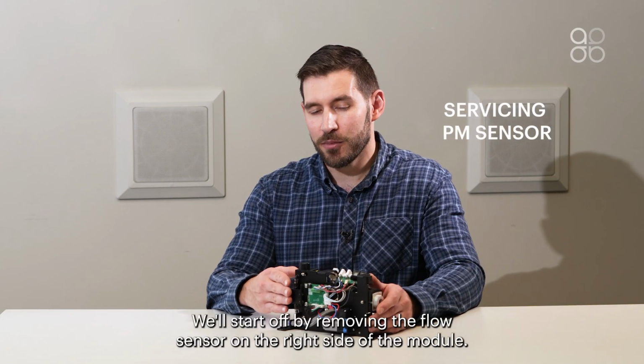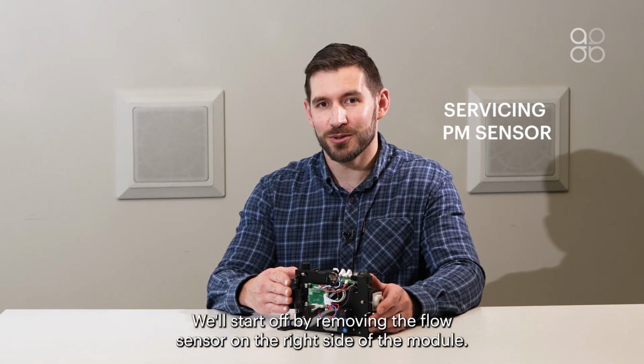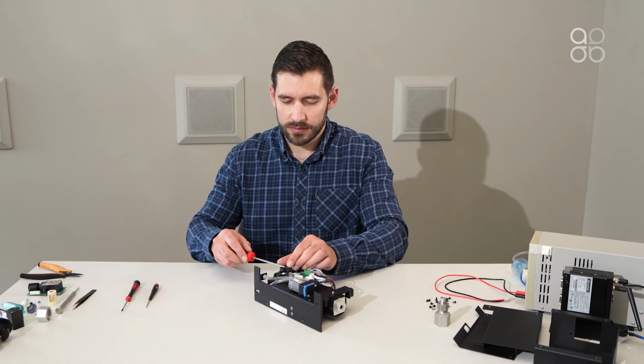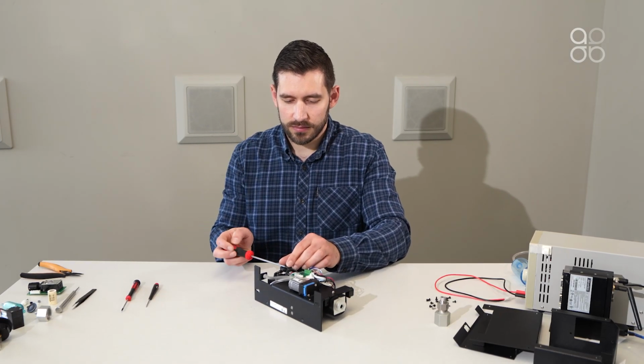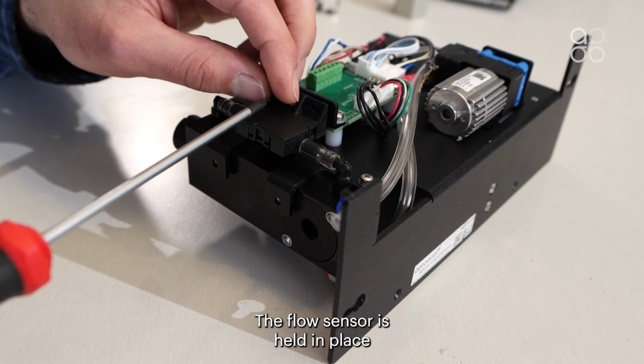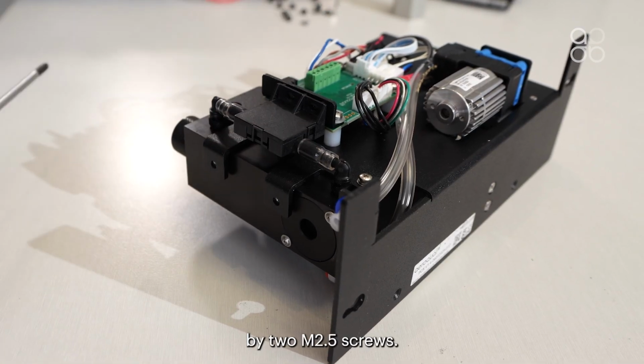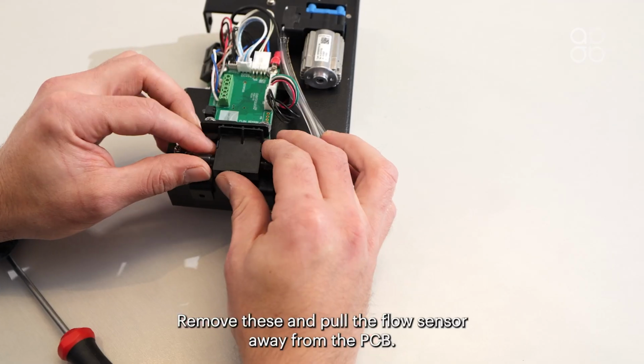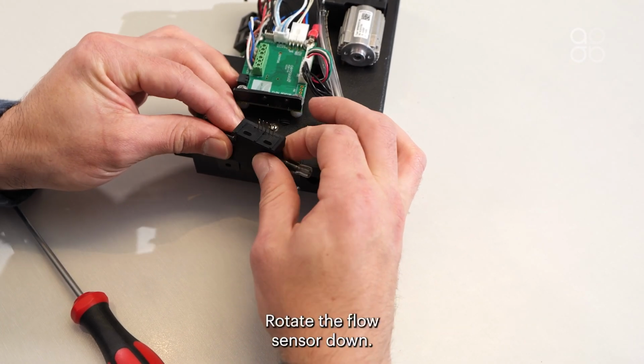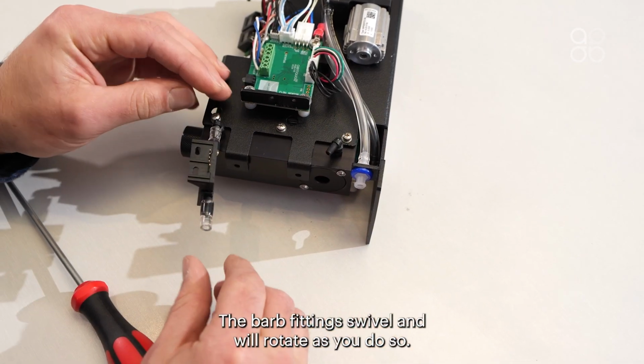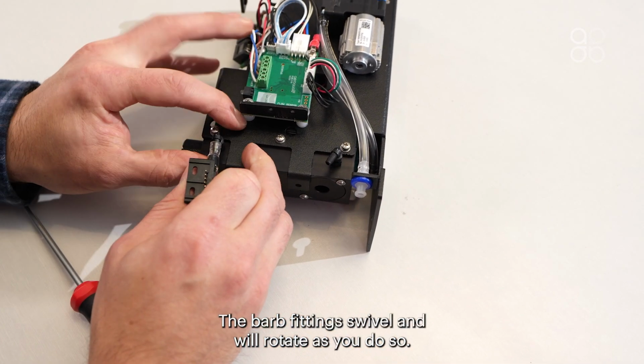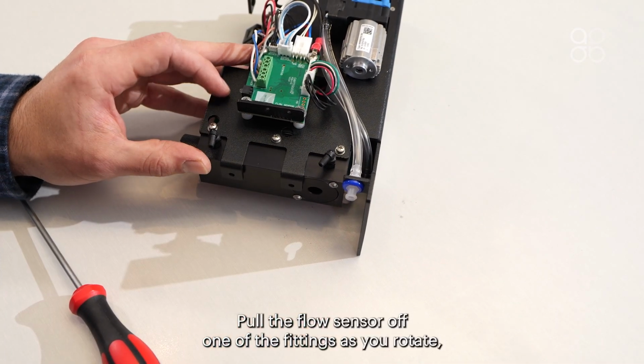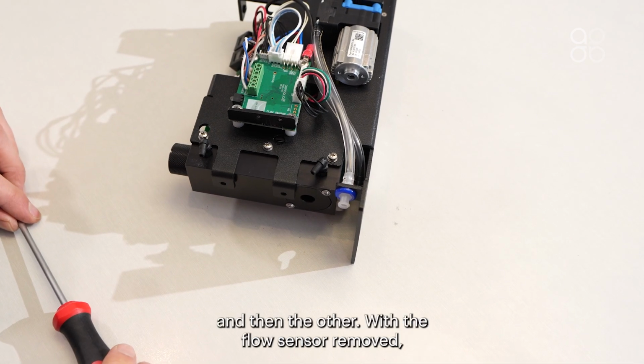We'll start off by removing the flow sensor on the right side of the module. The flow sensor is held in place by 2 M2.5 screws. Remove these and pull the flow sensor away from the PCB. Rotate the flow sensor down. The barb fittings swivel and will rotate as you do so. Pull the flow sensor off one of the fittings as you rotate, and then the other.